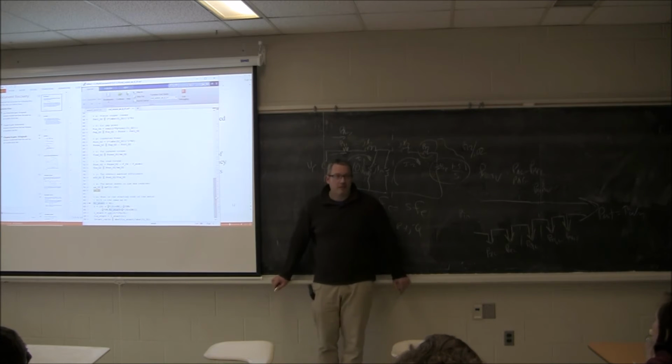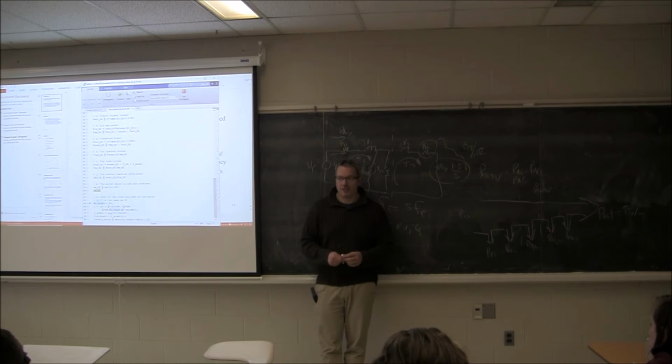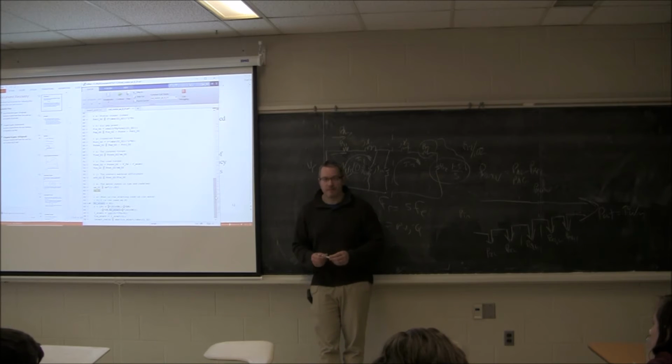So how do we solve for the KVA code? What does the starting KVA code mean? When you first energize the motor, how much power is it drawing, how much current does it draw, and then you have a ratio. You have to do the KVA code calculation, which is KVA per horsepower.